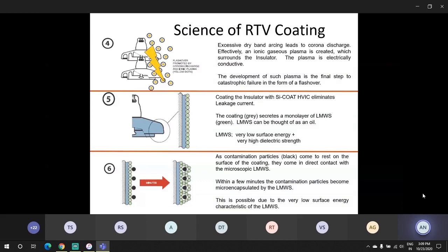This rich concentration of silicone polymers secretes a monolayer of silicone molecules, which we call in technical terms the low molecular weight silicones. And it has two distinct properties. It has a very low surface energy and a very high dielectric strength. So when there is contamination deposited on the insulator surface, the low molecular weight silicone encapsulates the contaminant and prevents it from coming in contact with the moisture.